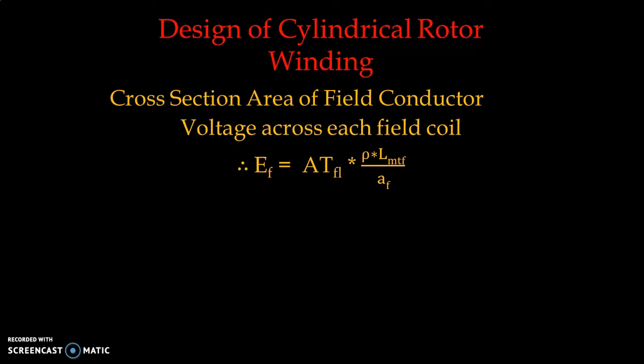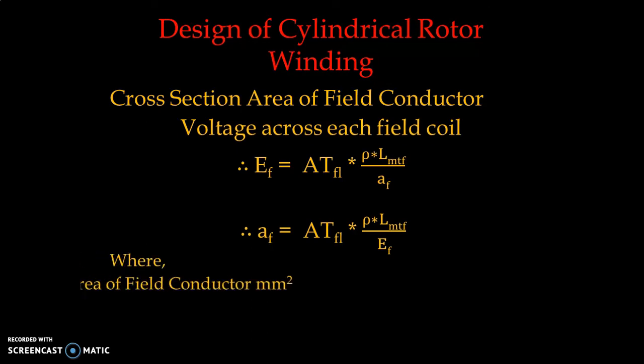ATfl is the full load field ampere-turns already estimated. ρ is the resistivity of copper, and Lmtf has been calculated with the empirical formula. Ef — the voltage across each field coil — was found as (0.8–0.85)×Ve/P. Using this equation, the cross-section area of the field conductor Af (in mm²) is straightforwardly calculated. The resistivity of copper is used since the conductors are typically copper.